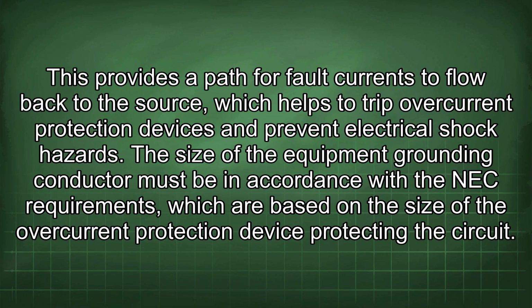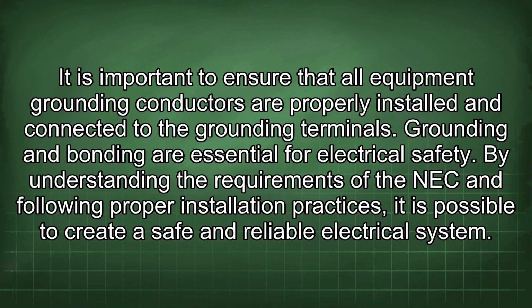The size of the equipment grounding conductor must be in accordance with the NEC requirements, which are based on the size of the overcurrent protection device protecting the circuit. It is important to ensure that all equipment grounding conductors are properly installed and connected to the grounding terminals. Grounding and bonding are essential for electrical safety.